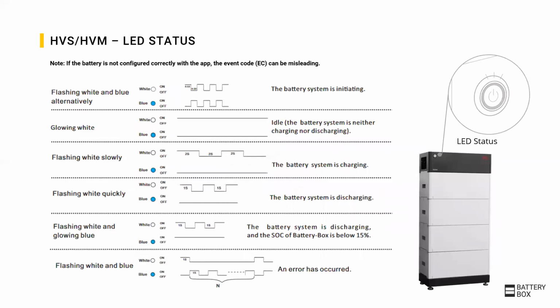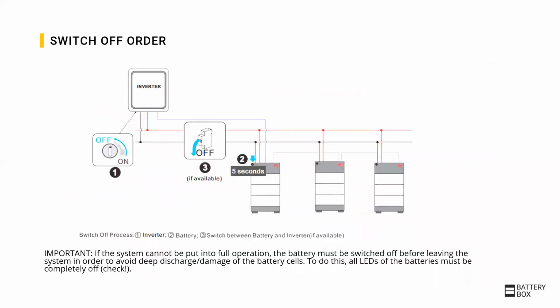When the battery is on, the LED on the BCU will show a status. White blinking is, for example, normal for charging or discharging. A white and blue flashing is normal for the startup phase or when the SoC is low. But based on the sequence, a white and blue blinking can also show an event code. For this, the number of blue blinks between white blinking has to be counted. In the service guideline, you will find further information and what to do.